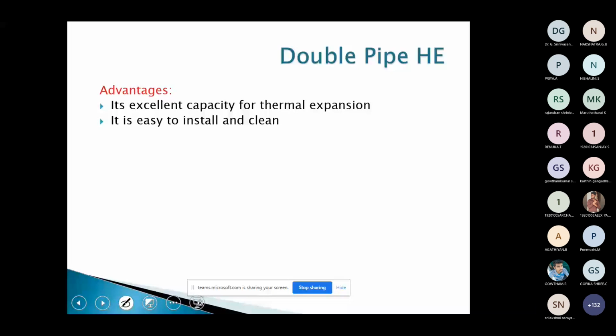During the course of the operation, after some period of time, there will be formation of fouling or scaling inside the tubes. That will reduce the heat transfer efficiency. So it should be cleaned periodically in order to maintain the process efficiency or heat transfer rate, whatever it may be. The periodic cleaning should be done based on the scale formation. Cleaning is very easy as far as double pipe is concerned, and it also has excellent capacity for thermal expansion.